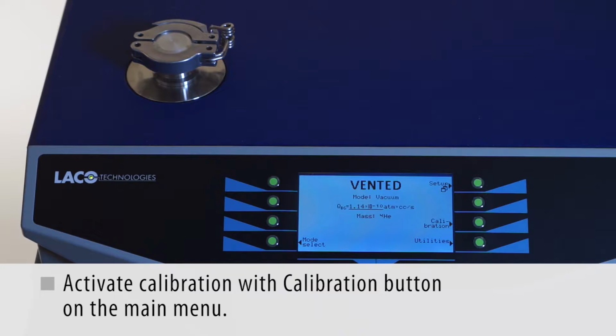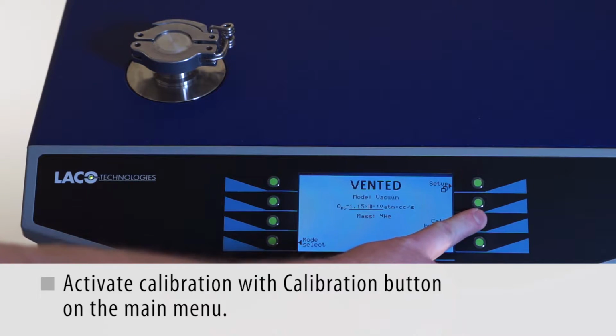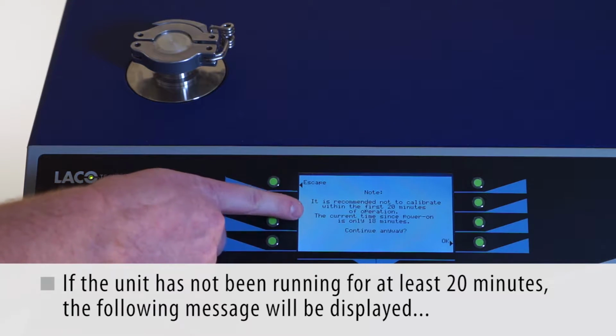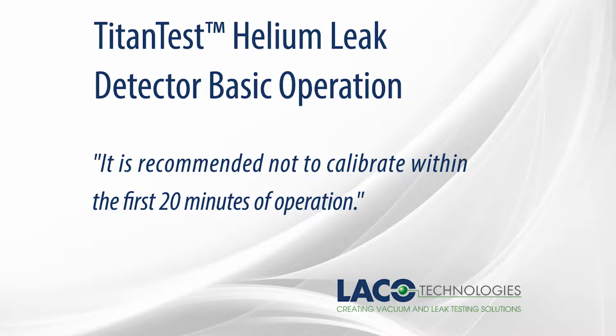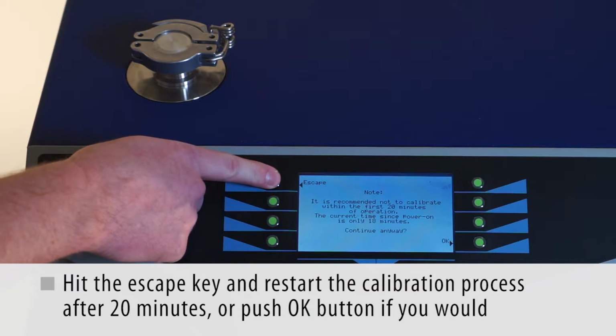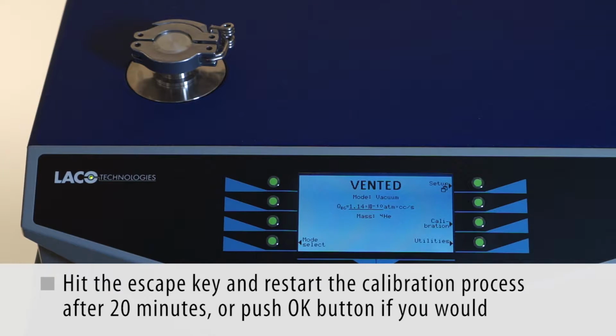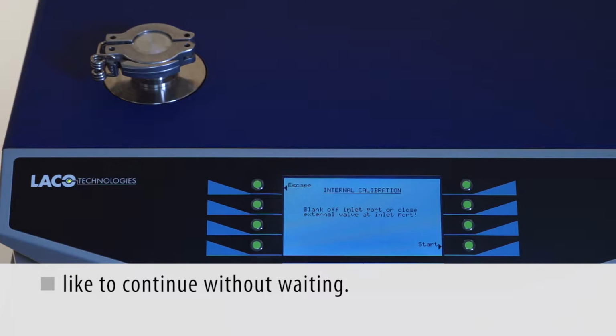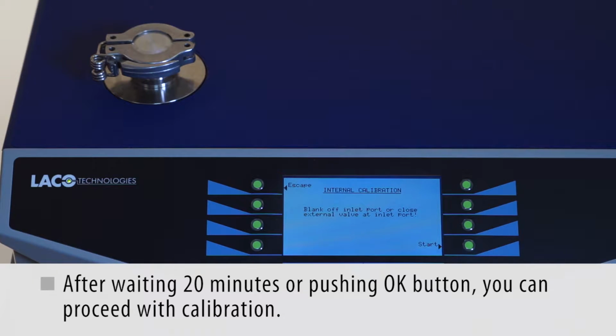Activate calibration with calibration button on the main menu. If the unit has not been running for at least 20 minutes, the following message will be displayed. It is recommended not to calibrate within the first 20 minutes of operation. Hit the escape key and restart the calibration process after 20 minutes, or push the OK button if you would like to continue without waiting. After waiting 20 minutes or pushing the OK button, you can proceed with calibration.